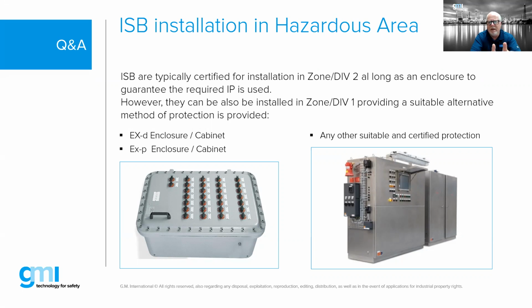However, we might need to put them in a zone 1 area. Maybe that cable run has to be kept much closer than we thought. Then we would have to take those barriers and potentially install them inside a flameproof enclosure, or in the case of the right-hand side, inside some sort of pressurized Ex p enclosure. So there are different ways. Sometimes we can just install them in a safe area and have no issues. But in other cases, we do need to install them in a hazardous location. So we have to look at the marking on the barrier itself and figure out what it's suitable for, if anything. And if it's not, then we have to use some other protection concept to mount those associated apparatus inside.